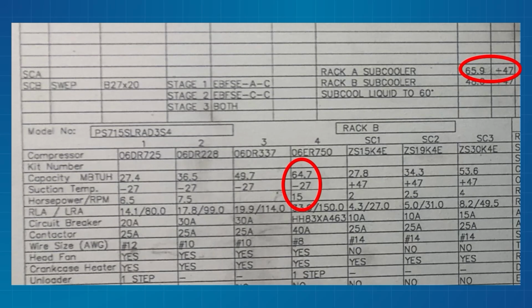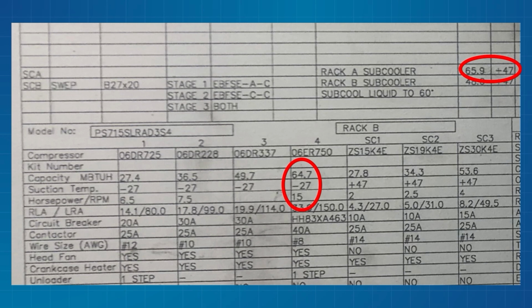Well, here on this rack, I just happen to have on compressor number 4, I've got a subcooler. I've got a compressor that's about the same capacity refrigeration-wise, about 5.5 tons. So I've got 5.5, 5.5, call those pretty dang close to the same. This one is my suction on the rack, minus 27. It's a cold rack, got bunkers and ice cream on this, it's a minus 27-degree rack. It is doing that with 15 horsepower. This is what we were talking about: running a lower suction pressure causes an exponential increase in power consumption, or loss of efficiency, however you want to look at it. Here's an example: I've got a 15 horsepower compressor that's only giving me 5.5 tons, but it's doing it at minus 27. Does that make sense?